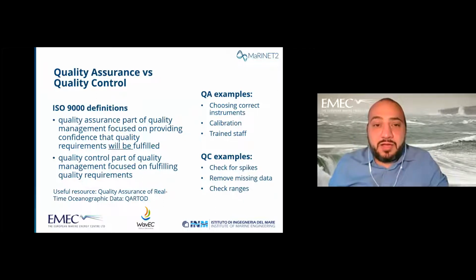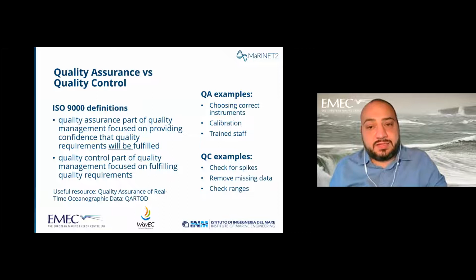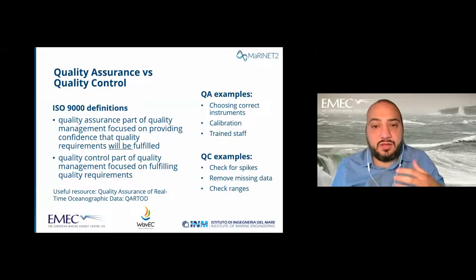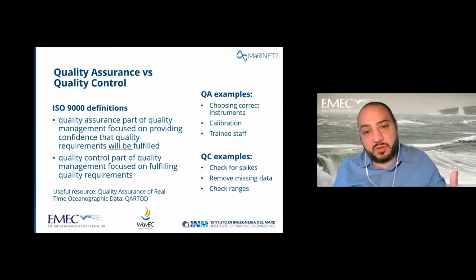But the giveaway here is the bit which says "will be". Quality assurance is what steps you can take to make sure that the measurements that will be done will be up to scratch, will meet the criteria you want them to meet, will be of really high quality. That's at the preparation stage, during the measurements, and so on. Quality control is the post-deployment, post-data collection bit. At that point, you take the data and make sure it's of high quality. You get rid of all the errors you can find in the data, and you're confident you can use it now. So another giveaway is assurance: you make sure the measurements will be okay. And control: you control after you collect the data.